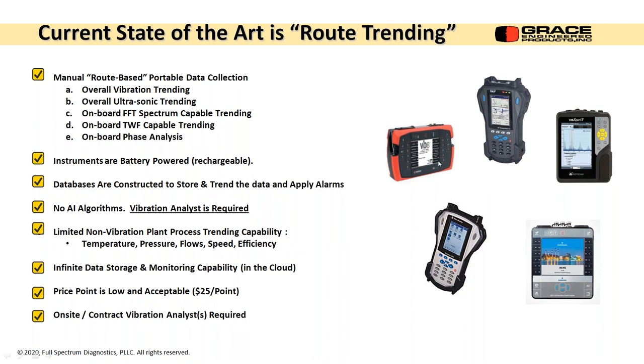Databases were constructed with these, so we're uploading and downloading data constantly. They don't really have algorithms. They have some statistical analysis they can use, but you do have to have a vibe guy that knows what he's doing. Infinite storage. And storage really isn't an issue anymore with hard drives being as big as they are. Price point is low and acceptable. And when you throw all the costs in, I came up roughly at about $25 a point, which is what, $400 a machine? No, $300, sorry. So not bad. On-site or contract vibration analysis is required, yeah. There's still a place for that.